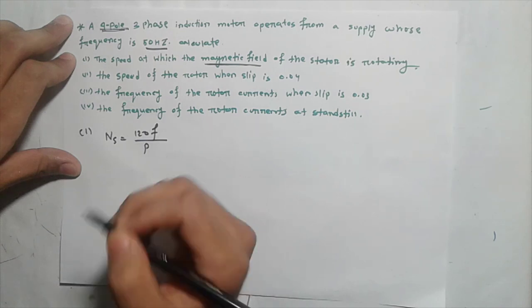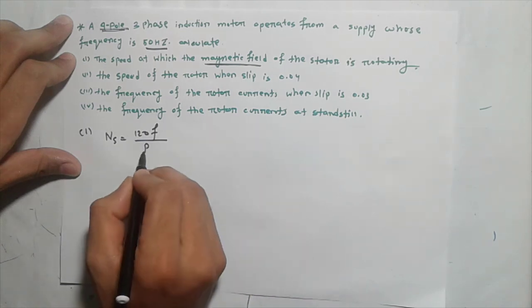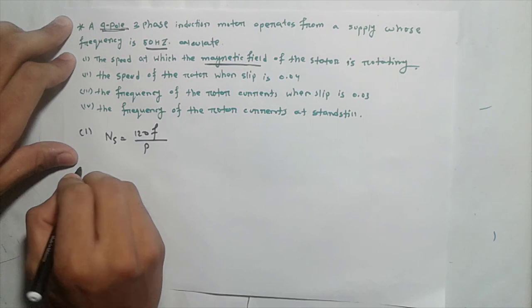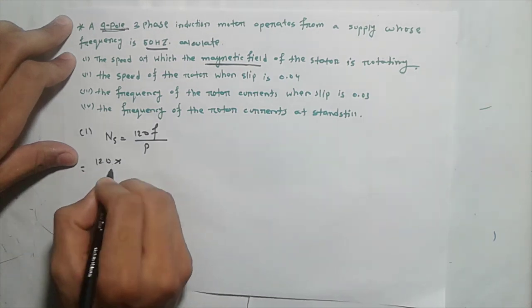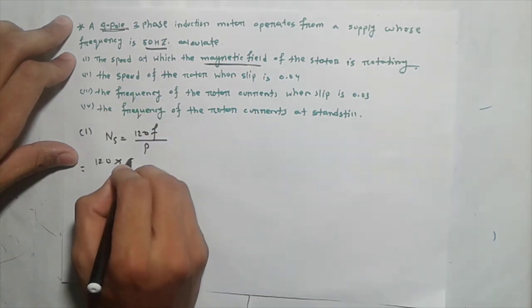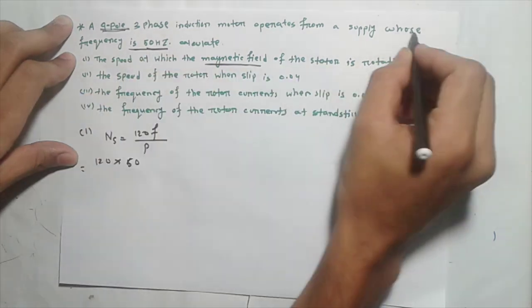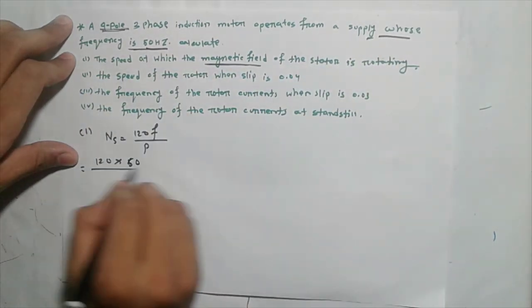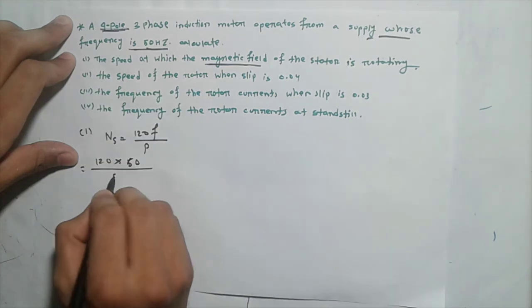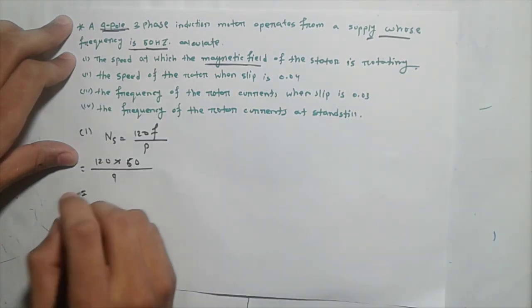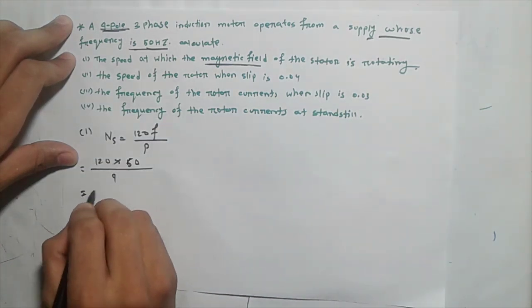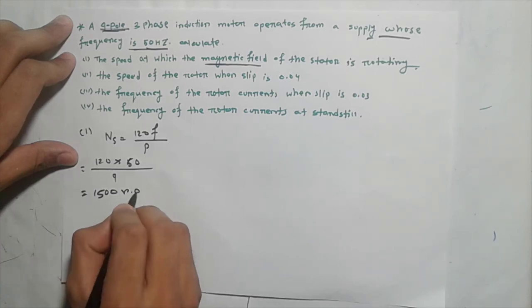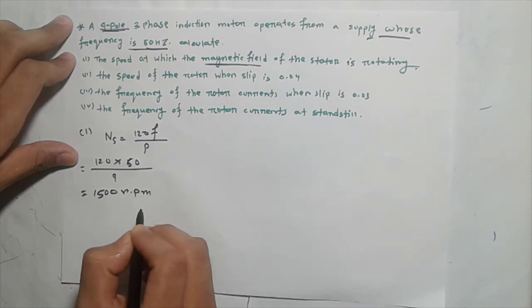The synchronous speed formula is: Ns = 120F / P, where F is the supply frequency and P is the number of poles (not pole pairs). With F = 50 Hz and P = 4 poles, we get the synchronous speed answer in RPM.